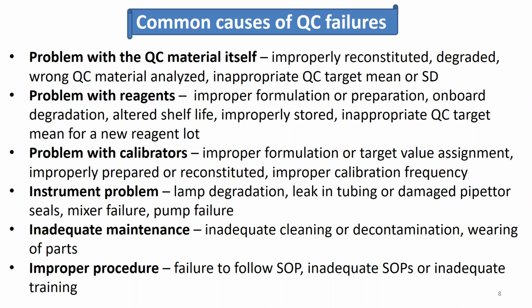QC failures can also be caused by instrument problems, so things like degradation of the lamp if the lab is using a spectrophotometric method, a leak in instrument tubing or damaged pipetter seals, mixer failures, and pump failures. Or the lab could have an inadequate maintenance frequency. So inadequate maintenance, inadequate cleaning or decontamination, wearing of parts without replacement in a timely manner. So all of those scenarios can cause QC failures. Improper procedures are also a common cause of QC failures. So failure to follow SOP, inadequate SOPs, or inadequate training for those SOPs.